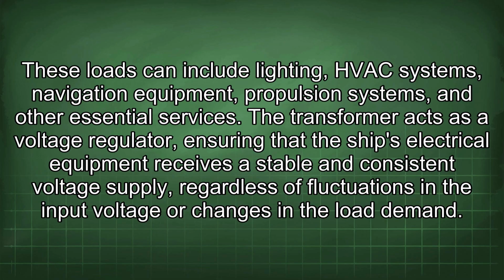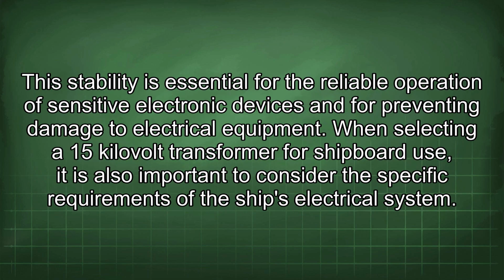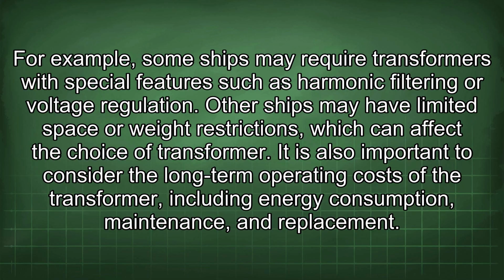The transformer acts as a voltage regulator, ensuring that the ship's electrical equipment receives a stable and consistent voltage supply, regardless of fluctuations in the input voltage or changes in the load demand. This stability is essential for the reliable operation of sensitive electronic devices and for preventing damage to electrical equipment. When selecting a 15 kV transformer for shipboard use, it is also important to consider the specific requirements of the ship's electrical system. For example, some ships may require transformers with special features such as harmonic filtering or voltage regulation.